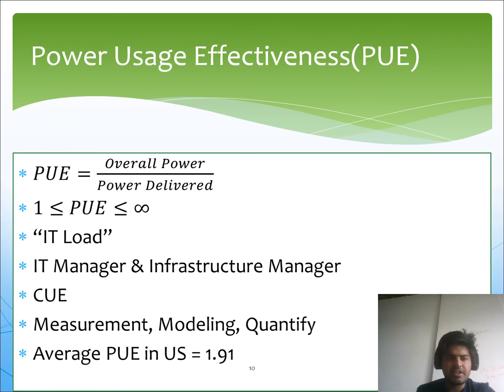PUE definition: the overall power drawn by the facility divided by the power delivered to the data center. PUE relates the total consumption of the installation with what is considered essential to the service, the computer servers, the IT load. It is the responsibility of the IT manager to reduce the consumption of the IT load, renewing servers, virtualizing, etc., and the responsibility of the infrastructure manager to reduce the auxiliary consumption, with more efficient equipment, free cooling, etc. Carbon usage effectiveness, CUE, defines CO2 emissions associated with data center losses.